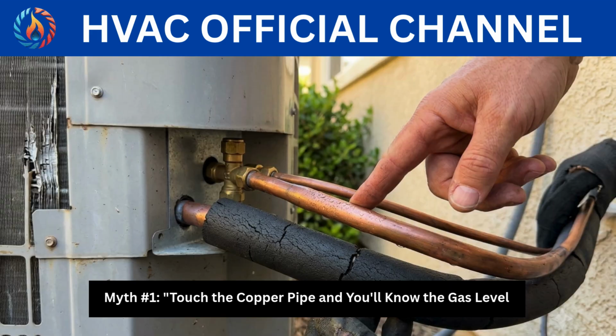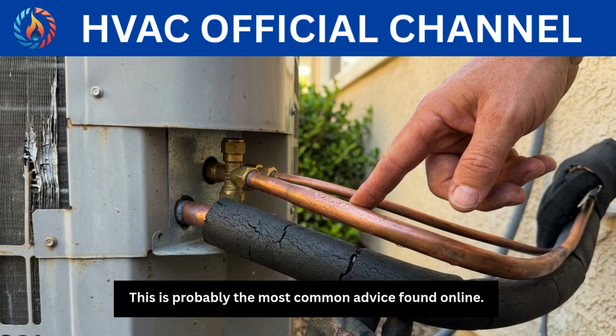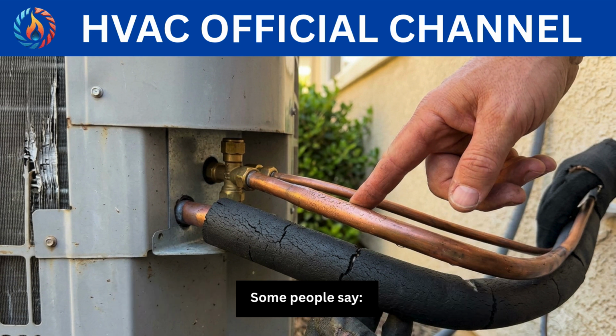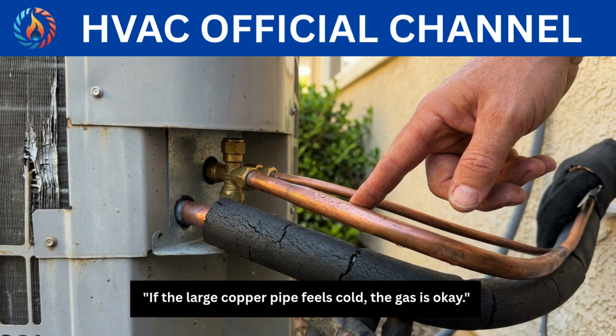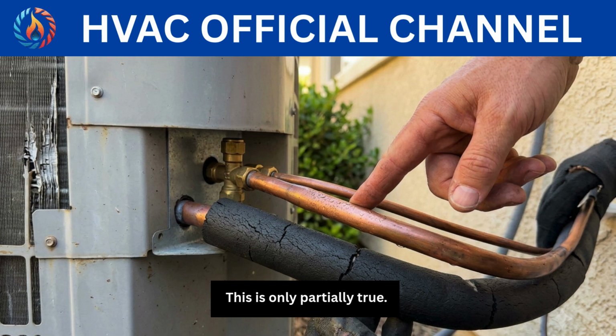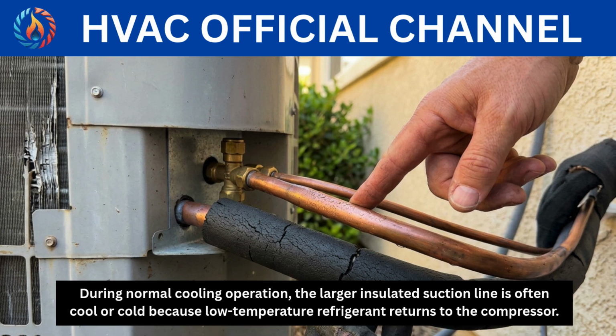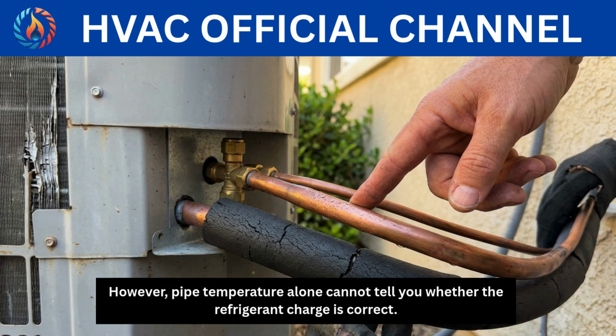Myth number 1. Touch the copper pipe and you'll know the gas level. This is probably the most common advice found online. Some people say, if the large copper pipe feels cold, the gas is okay. This is only partially true. During normal cooling operation, the larger insulated suction line is often cool or cold, because low-temperature refrigerant returns to the compressor. However, pipe temperature alone cannot tell you whether the refrigerant charge is correct.